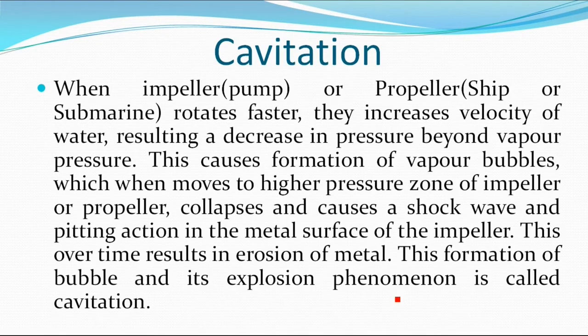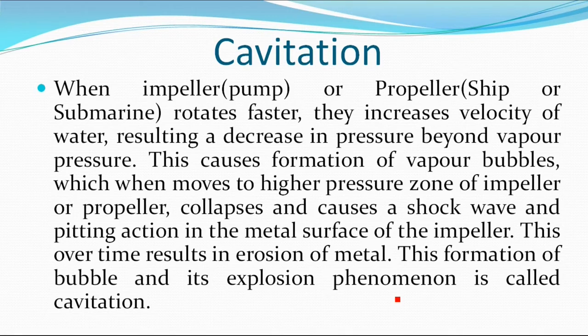Cavitation: when the impeller of a pump or propeller of a ship or submarine rotates faster, it increases the velocity of water, resulting in a decrease in pressure based on Bernoulli's principle. This causes formation of vapor bubbles, which when they move to a higher pressure zone of the impeller or propeller, collapse and cause a shock wave and pitting action on the metal surface of the impeller. Over time, this results in erosion of metal. This formation of bubbles and their explosion phenomenon is called cavitation.